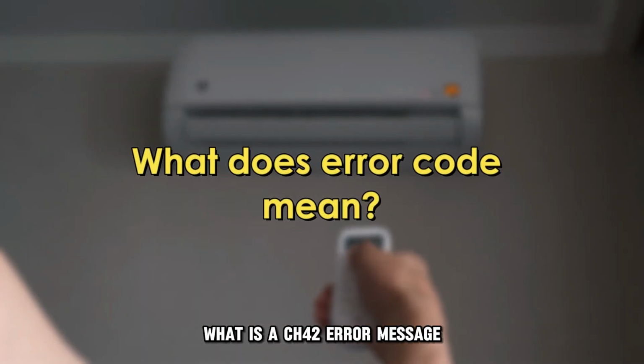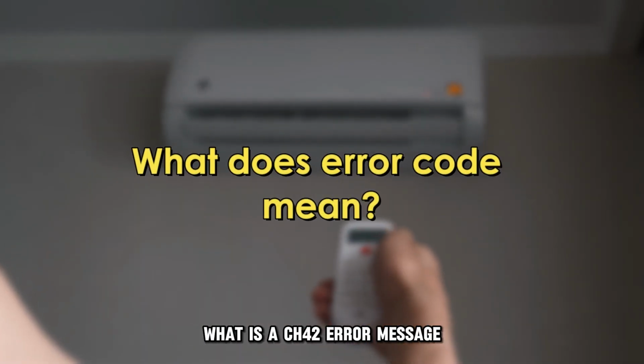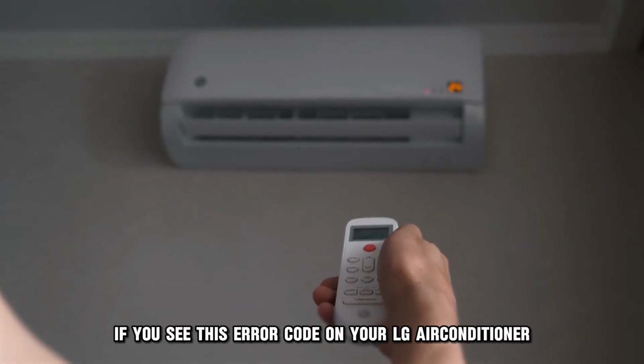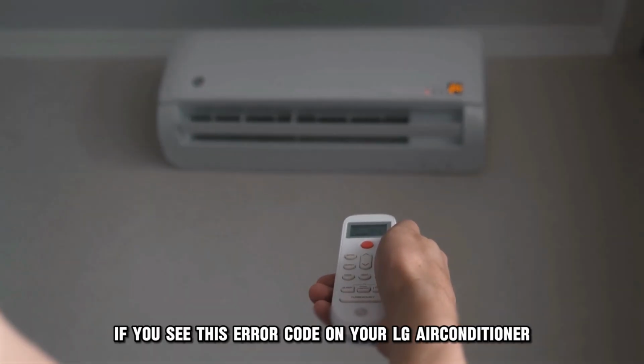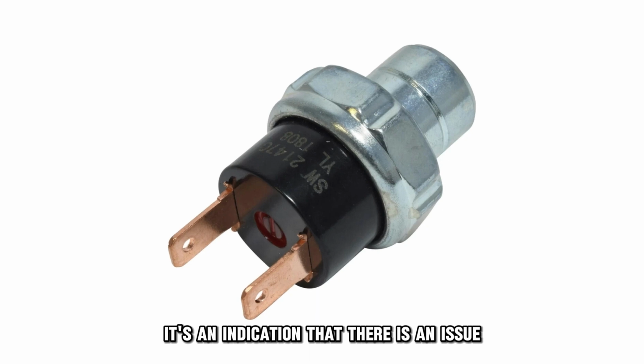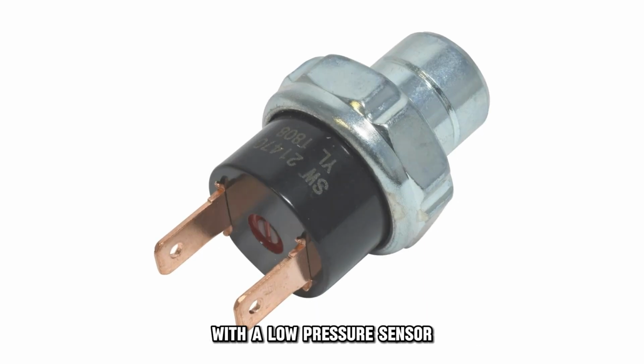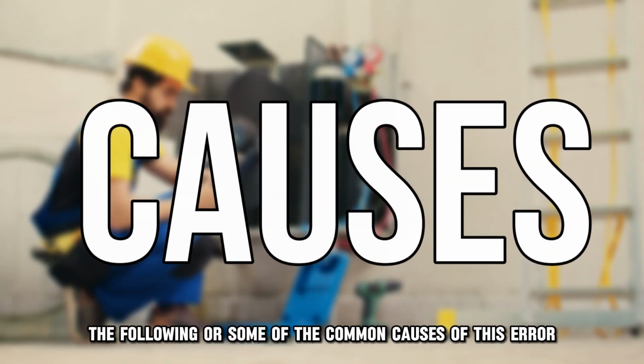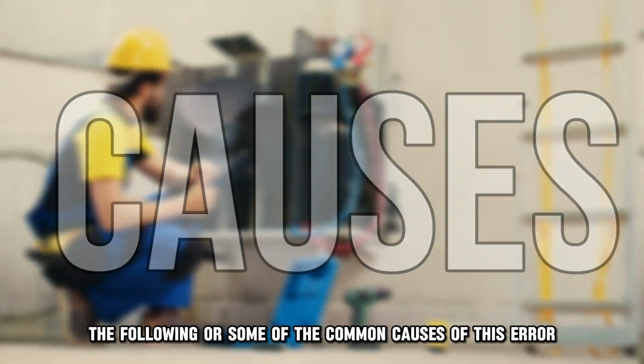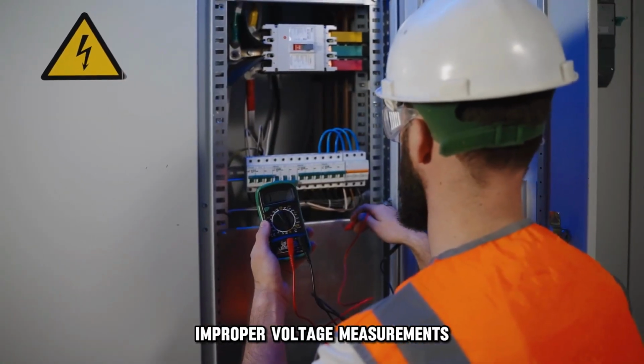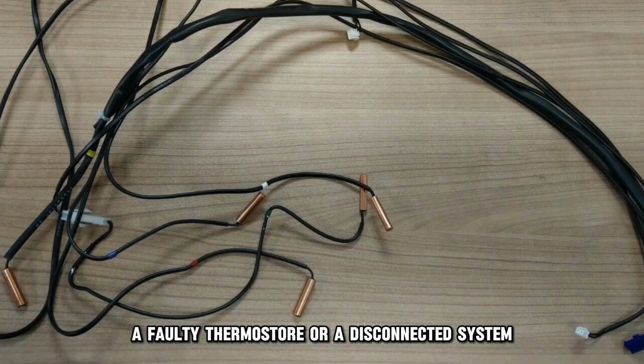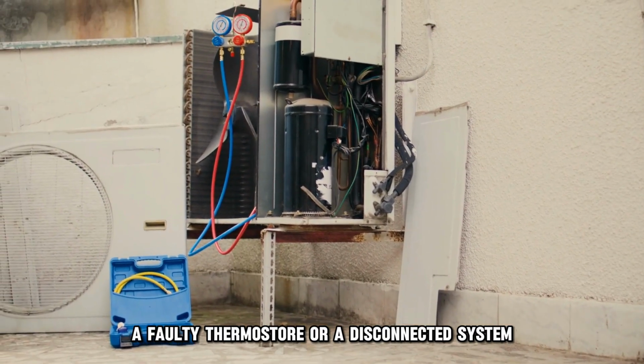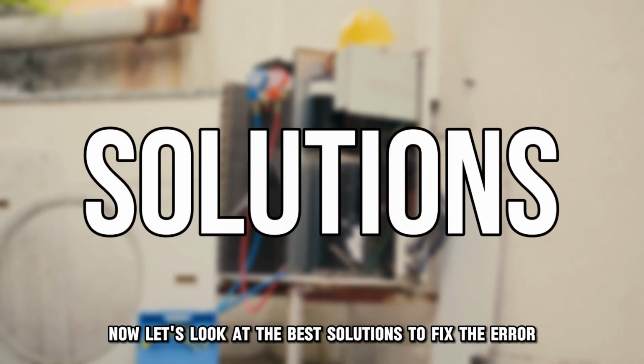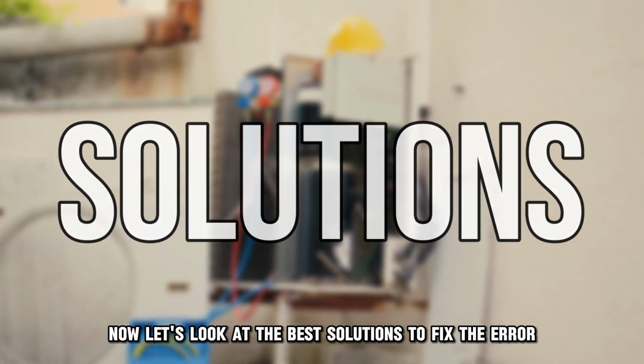But first, what is a CH42 error message? If you see this error code on your LG air conditioner, it's an indication that there's an issue with a low pressure sensor. Common causes include improper voltage measurements, a faulty thermistor, or a disconnected system. Now let's look at the best solutions to fix the error.